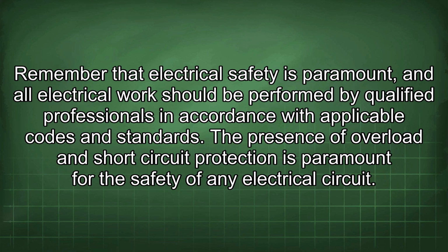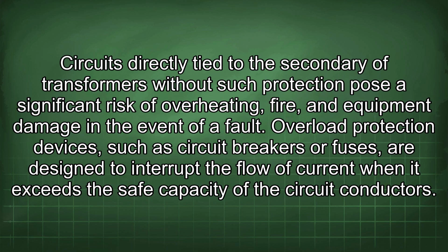The presence of overload and short-circuit protection is paramount for the safety of any electrical circuit. Circuits directly tied to the secondary of transformers without such protection pose a significant risk of overheating, fire, and equipment damage in the event of a fault.